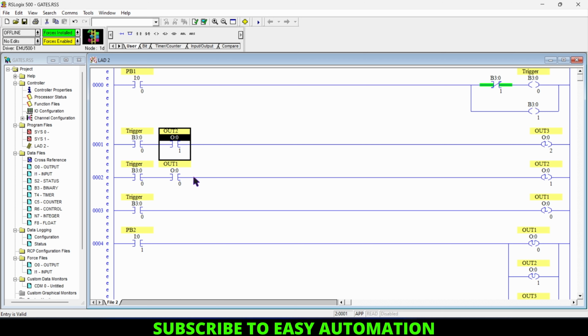Now what will happen here is, whenever I give our first trigger pulse, that trigger pulse will come here for these NO contacts, but the trigger pulse will only turn on this first output, because I have created one interlock between our second output and third output. So that's why our trigger pulse will only turn on our first output for the first triggering pulse. Now let's check our program.